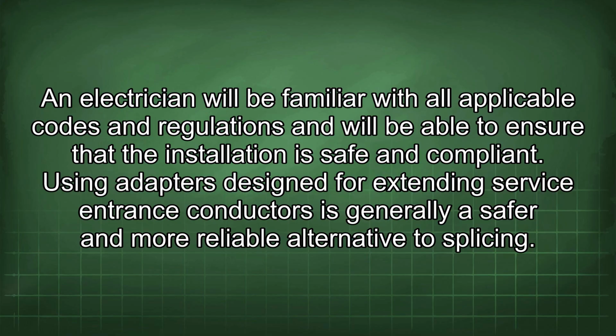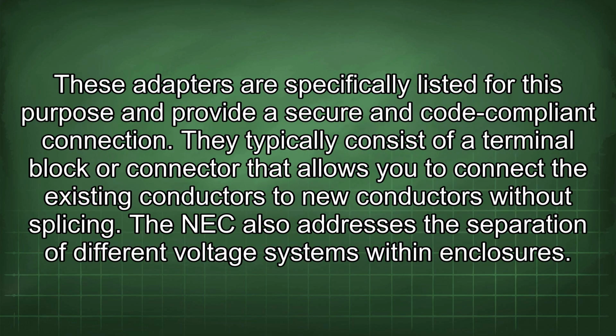Using adapters designed for extending service entrance conductors is generally a safer and more reliable alternative to splicing. These adapters are specifically listed for this purpose and provide a secure and code-compliant connection. They typically consist of a terminal block or connector that allows you to connect the existing conductors to new conductors without splicing. The NEC also addresses the separation of different voltage systems within enclosures.